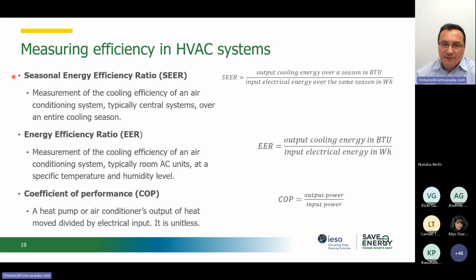And as you see, the formulas are fairly similar. One is showing this over a longer period of time, over a season, and it's defined based on certain methods, standards, and protocols to be able to compare equipment from various manufacturers. And this is what we see in, let's say, Energy Star equipment, the equivalent of the seasonal energy efficiency ratio. But as you notice in the formula, the units of measurement are funny. We use in the numerator BTU per hour, using the imperial system, and we use in the denominator watt-hour as a more popular unit for electricity, because the input in the heat pump is electricity, while the output heat is expressed in different units.